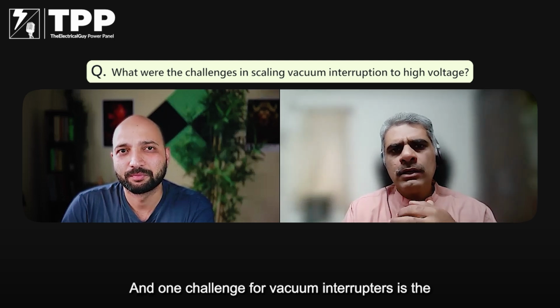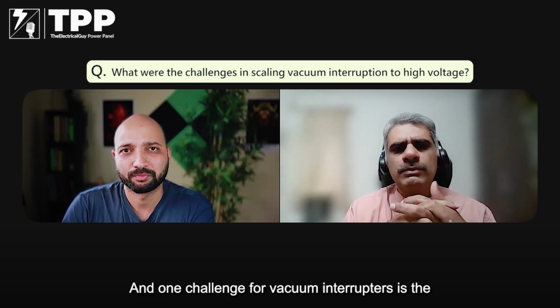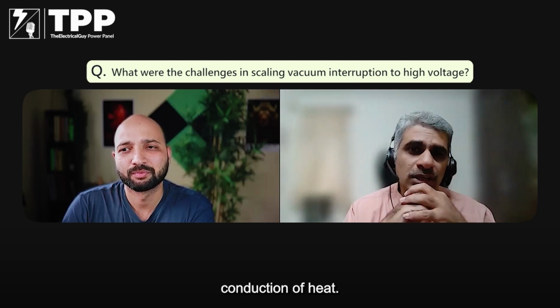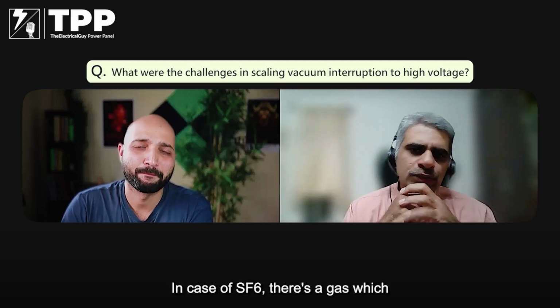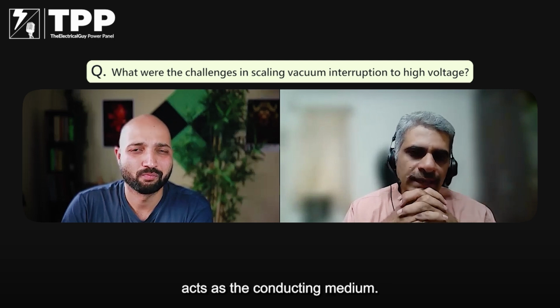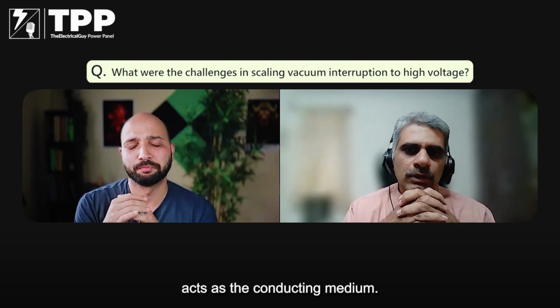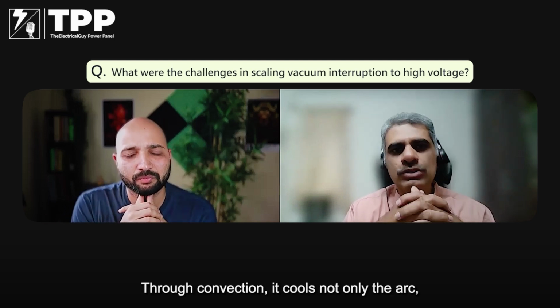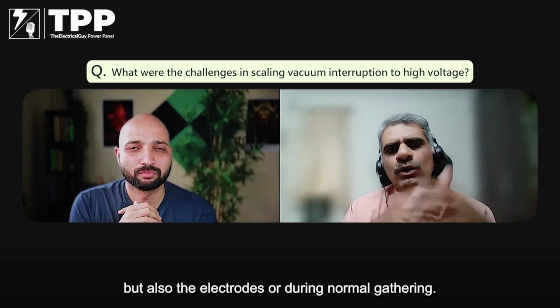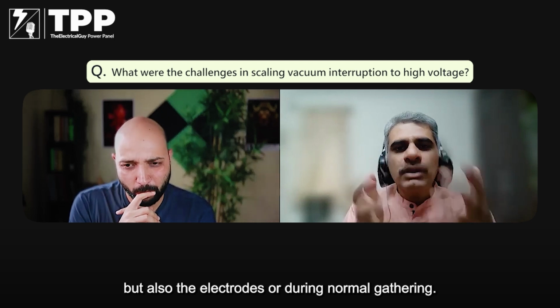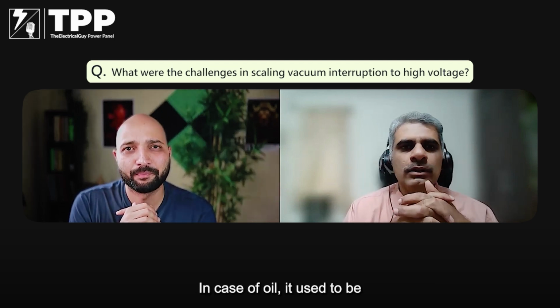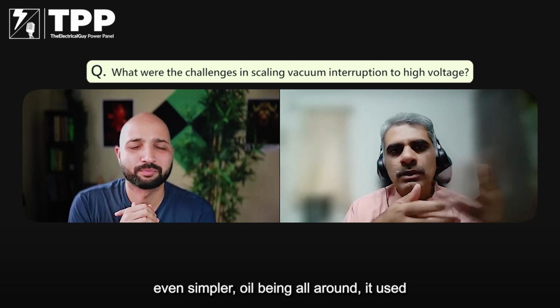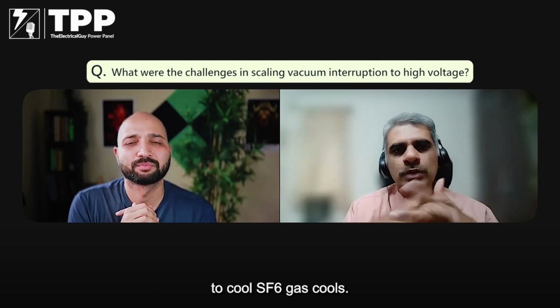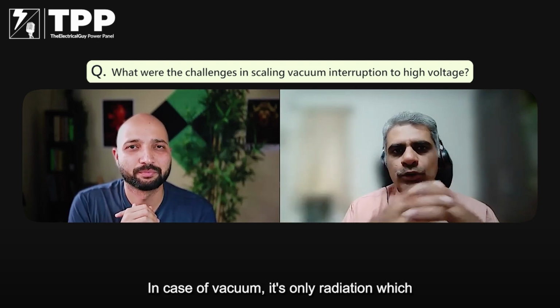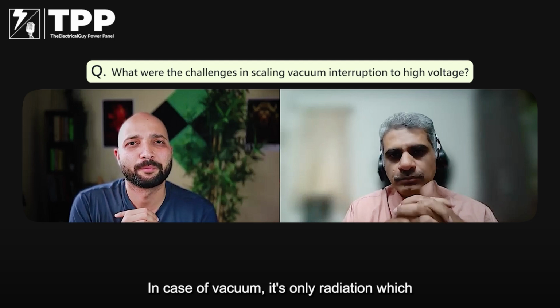And one challenge for vacuum interrupters is the conduction of heat. In the case of SF6, there's a gas which acts as the conducting medium. Through convection, it cools not only the arc but also the electrodes during normal current carrying. In the case of oil, it used to be even simpler. Oil being all around, it used to cool. SF6 gas cools. In the case of vacuum, it's only radiation.